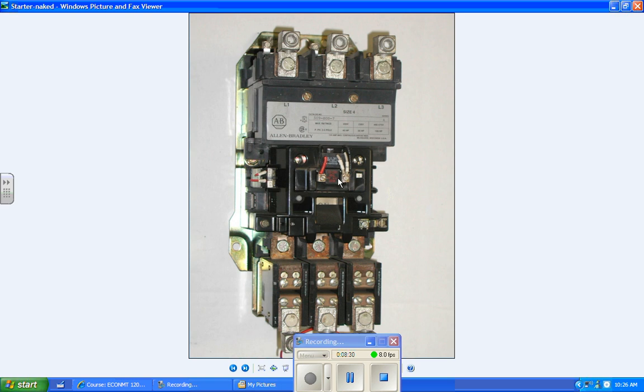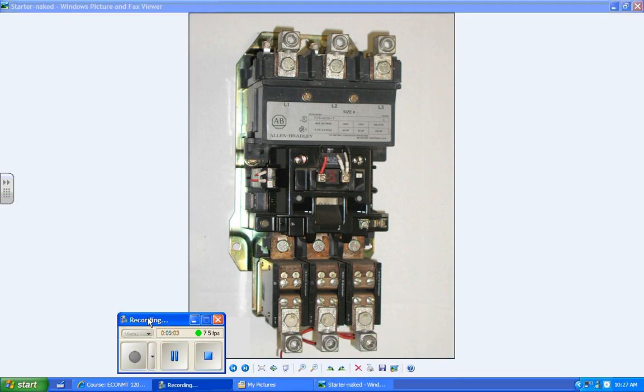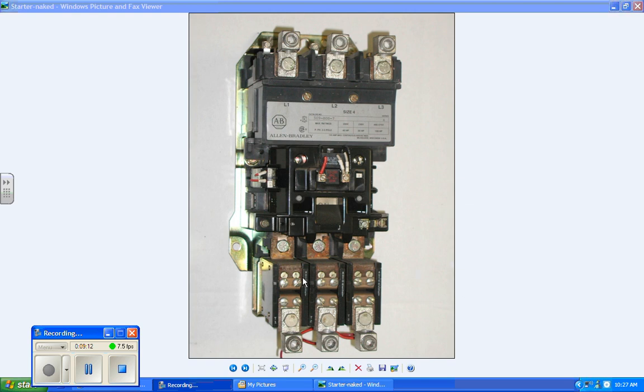Magnetic motor starters generally speaking will have a couple of things in common. They will all have a coil, which is what pulls the thing in and closes the power circuits. They'll have holding contacts, and the holding contacts keep the circuit closed. One of the things that a magnetic motor starter has that a relay does not is a holding contact. The other thing it has is this whole block down here - the motor overload relay.